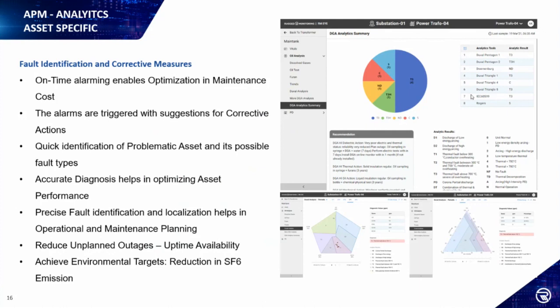If I get oil analysis data, whether it's coming from oil sampling or from an online dissolved gas analyzer, and use different analytical tools like duval triangles, duval pentagon, Rogers ratio, IEEE, IEC ratio, these tools help identify the possibility of a fault developing in the transformer, and then give a recommended action for it. Such analytics are available today.